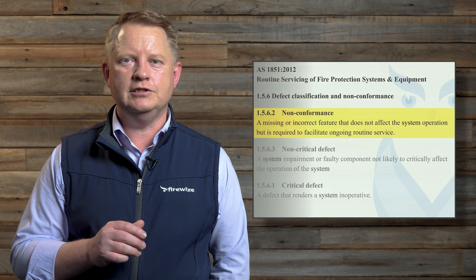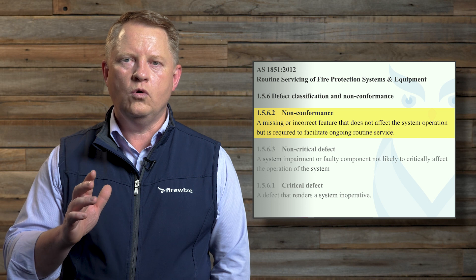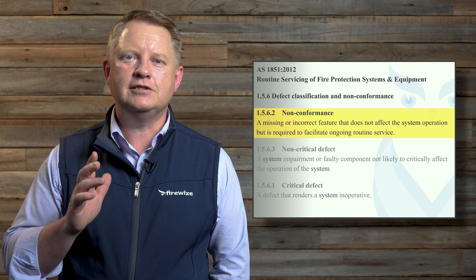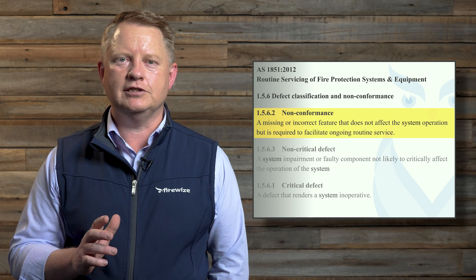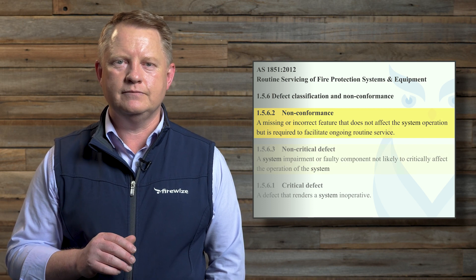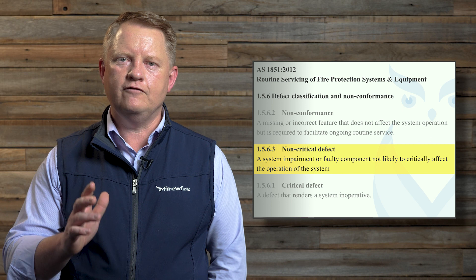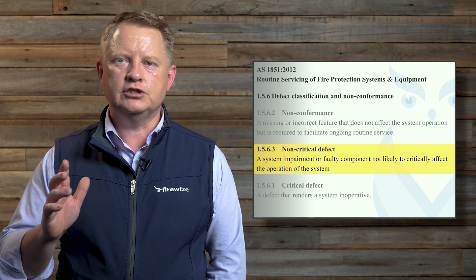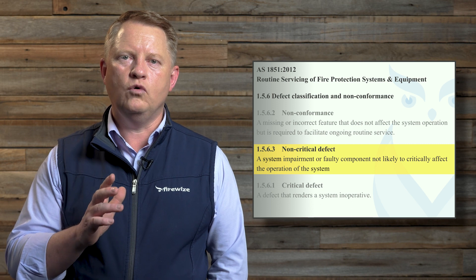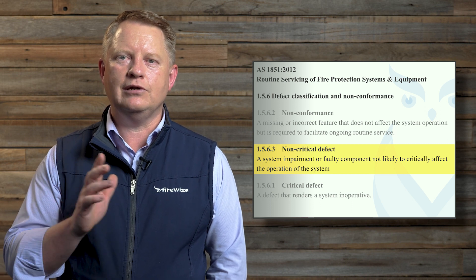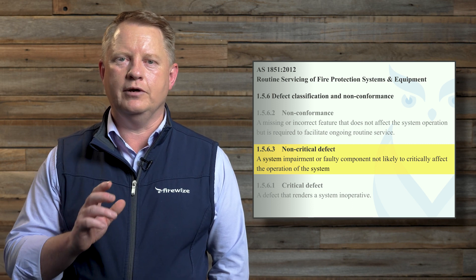In Clause 1.5.6.2 of AS1851 2012, a non-conformance is defined as missing information or an incorrect feature that does not affect the system operation but is required to facilitate ongoing routine service. Clause 1.5.6.3 describes a non-critical defect as a system impairment or faulty component not likely to critically affect the operation of the system.